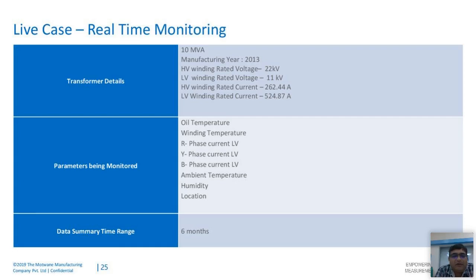Typically what we're monitoring here are the load currents, voltages, and the oil and winding temperature. Along with that, we also monitor the humidity and ambient temperature. This present analysis shows 6 months of data, which we'll use to demonstrate all the functionalities this solution can provide.